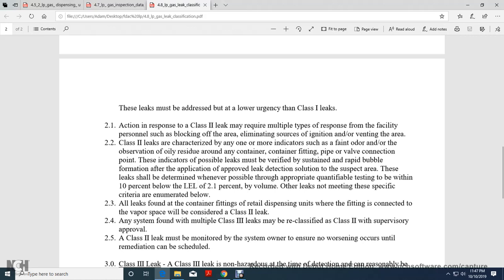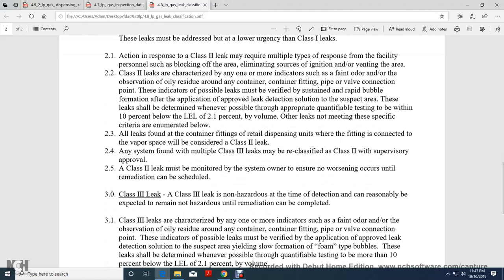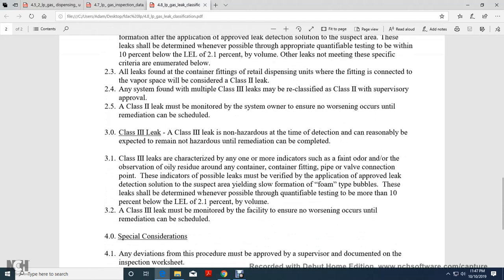Class 2 leaks are characterized by one or more indicators of faint odor or observation of oily residue around any container, container fitting, pipe or valve connection point. Indicated possible leaks must be verified by sustained and rapid bubble formation using a cumulative application-approved leak detection solution in the affected area. Leaks should be determined whenever possible through appropriate quantifiable testing within 10% of the low explosive limit of 2.1% by volume.